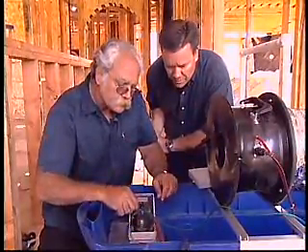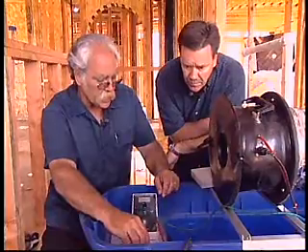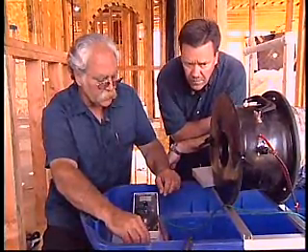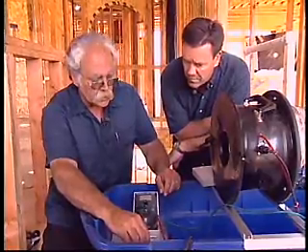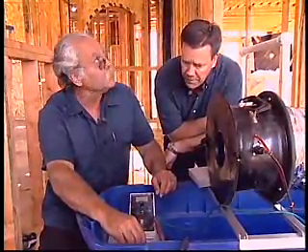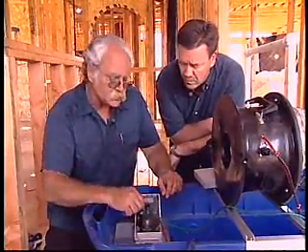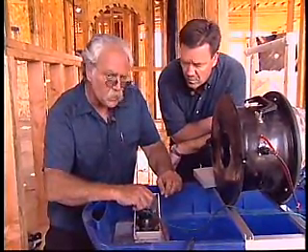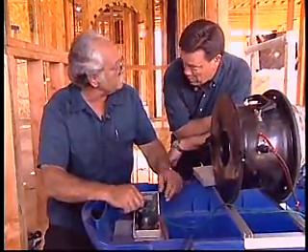This device here is called a manometer — a digital manometer. It's a very accurate pressure gauge, simply measuring pressure difference from one point to another. Right now I'm testing the ducts to a reference pressure of 25 pascals. Once we achieve that pressure, we switch to a different mode to read how much leakage there is.